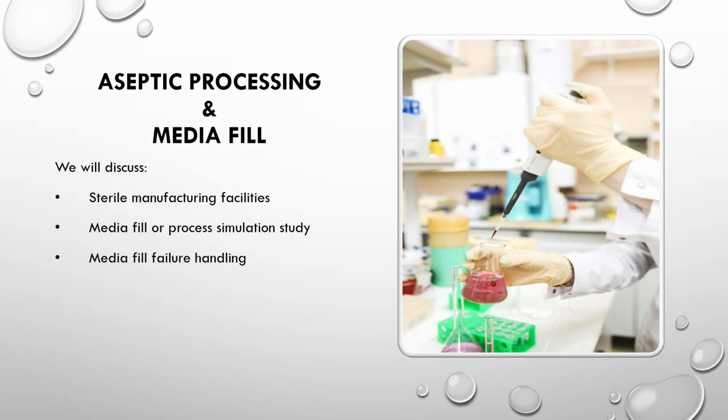Instead of filling the vials with real medicine, scientists fill them with sterile nutrient media, a liquid that microorganisms love to grow in. Now imagine this. If even one microorganism accidentally enters the vial during filling, the nutrient media will allow it to grow and the vial will become cloudy or show microbial growth after incubation.